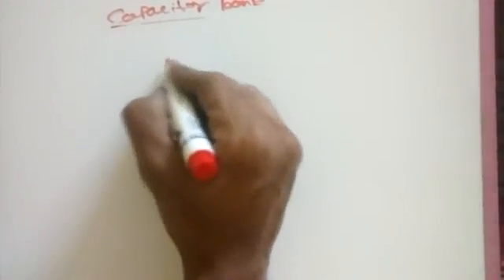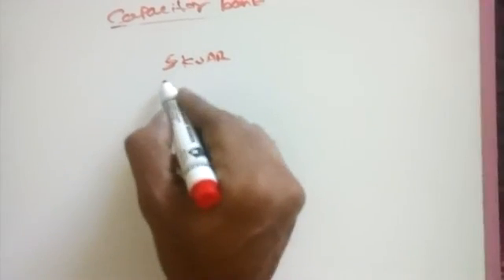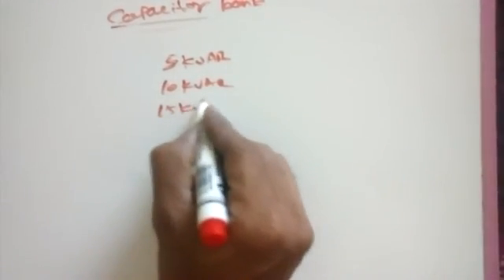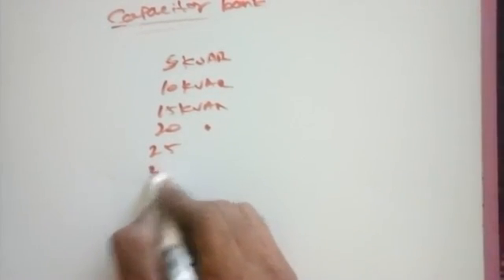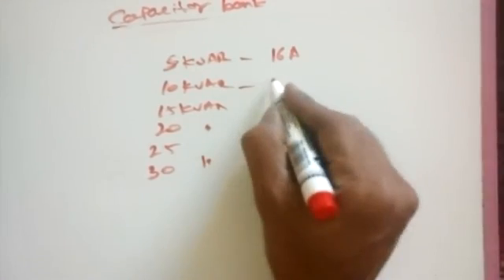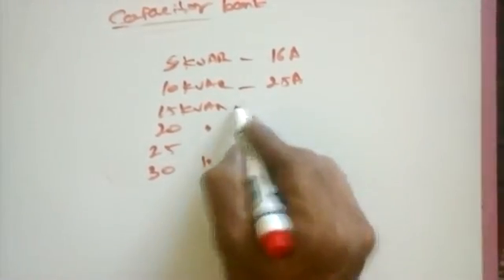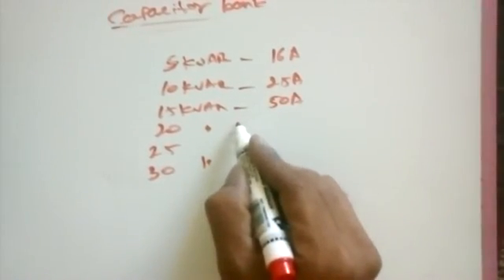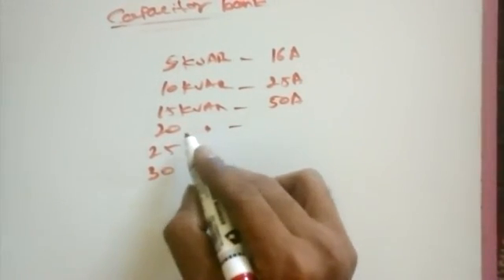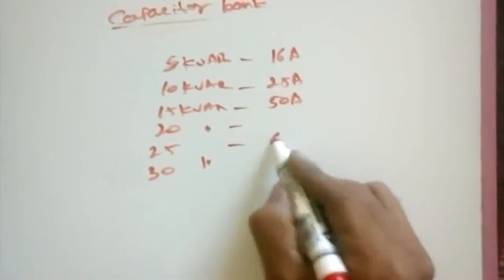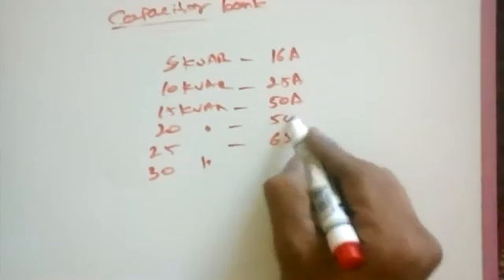First one is 5 kVR in first step, 10 kVR, 15 kVR, 20 kVR, 25 kVR. In 5 kVR we choose 16 ampere fuse link. In 10 kVR we choose 25 ampere fuse link. In 15 kVR we choose 50 ampere fuse link. In 25 kVR we choose 63 ampere. In 20 kVR we choose 50 ampere.